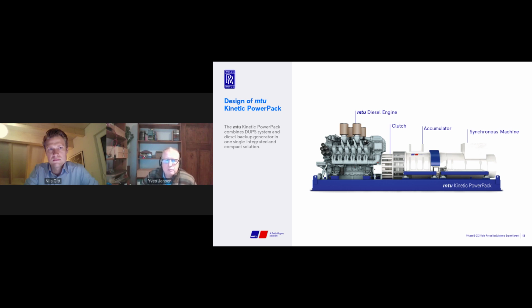The MTU Kinetic Power Pack is a dynamic UPS. In case of grid failure, it will provide electrical power to the critical load without interruption. It consists of an MTU diesel engine, a synchronous machine, and in between those two, a clutch and a kinetic accumulator. The accumulator is a rotating mass from which, in case of mains failure, energy is taken during the time it takes to start the diesel engine.